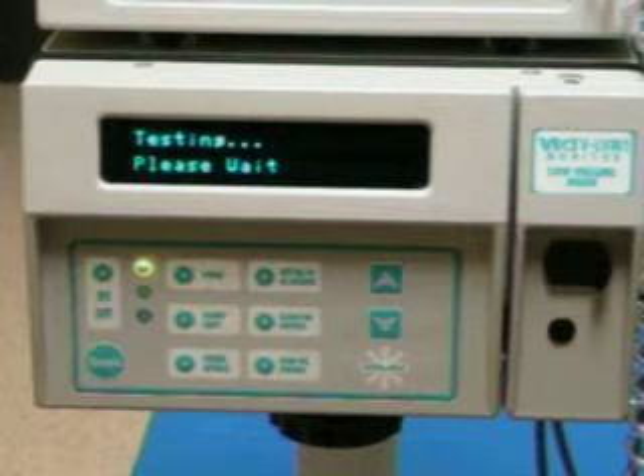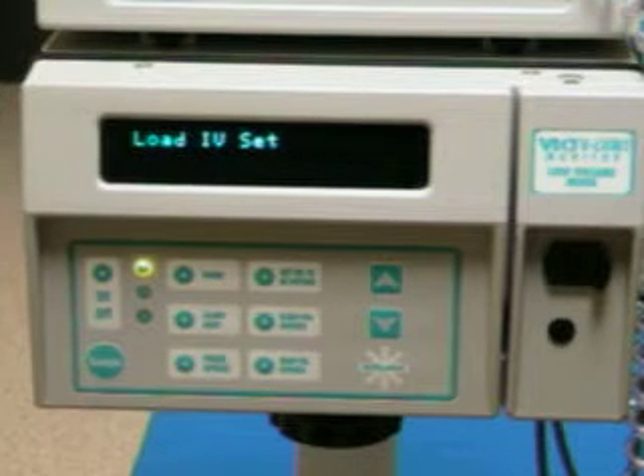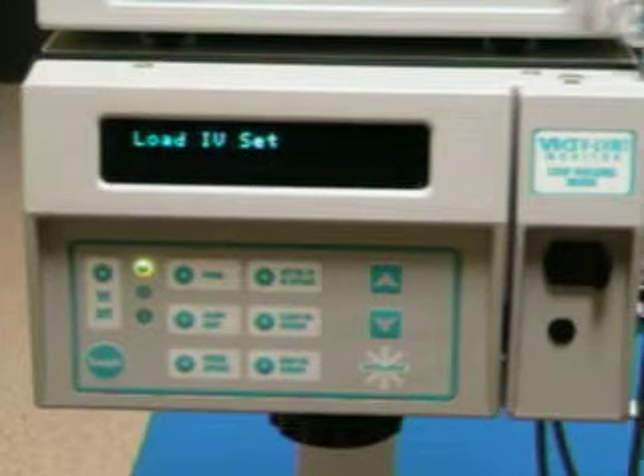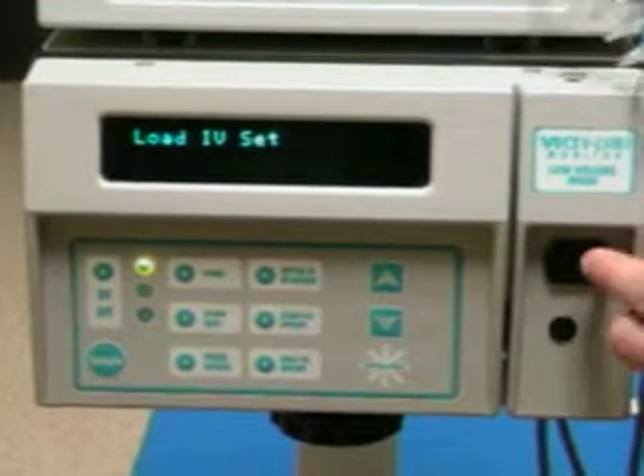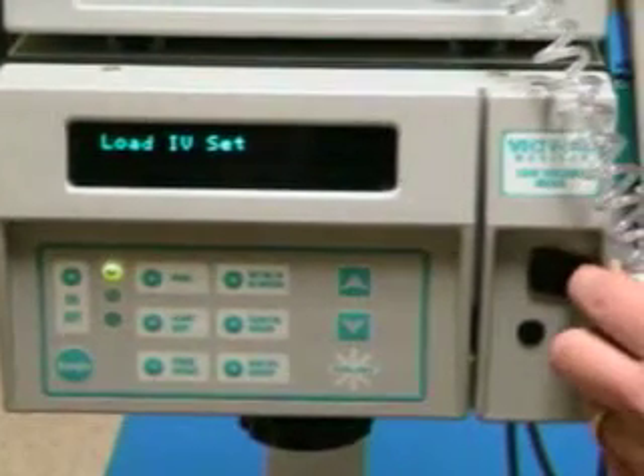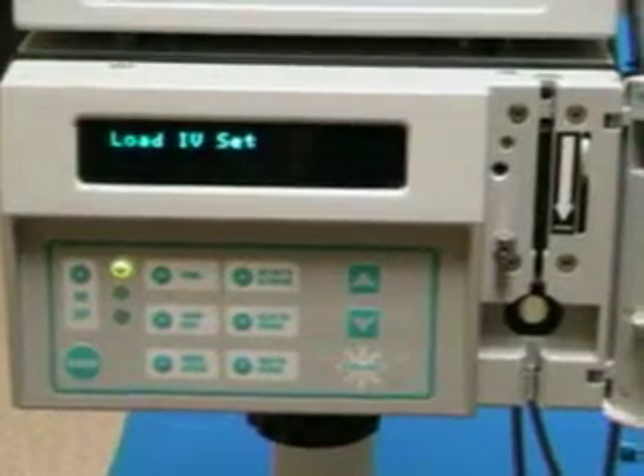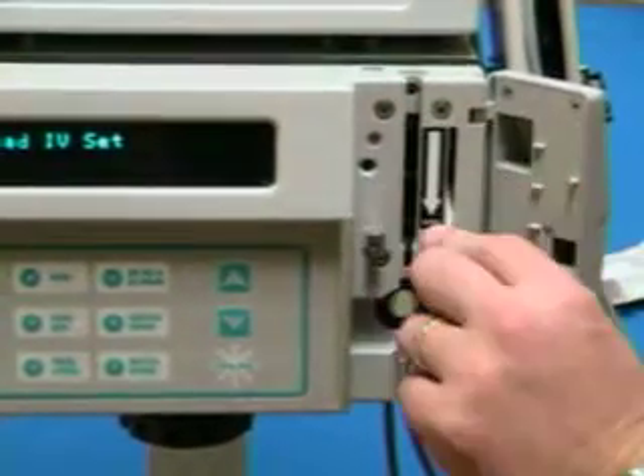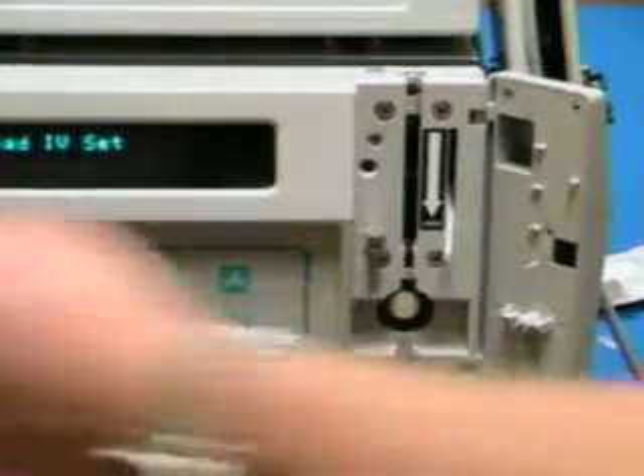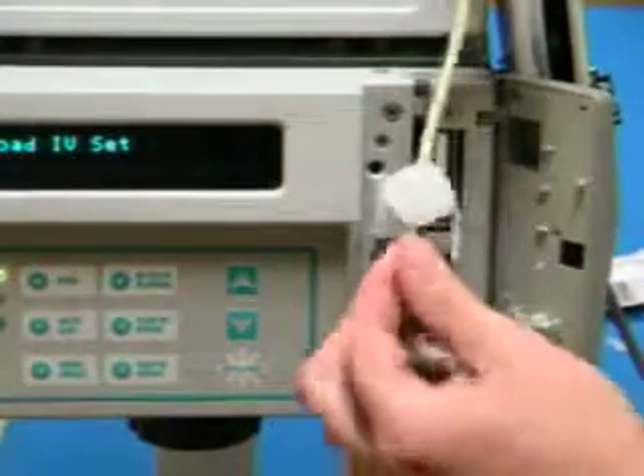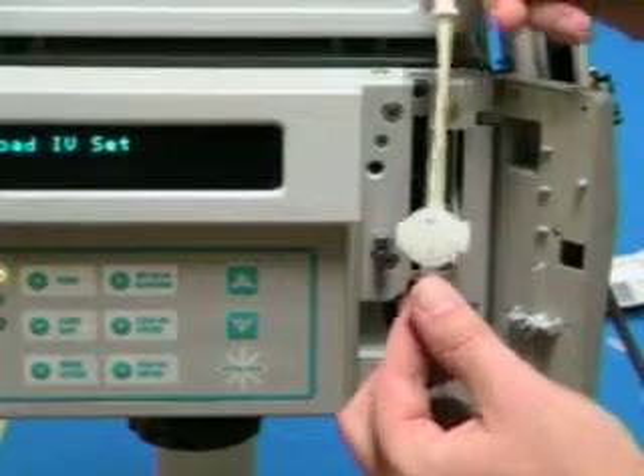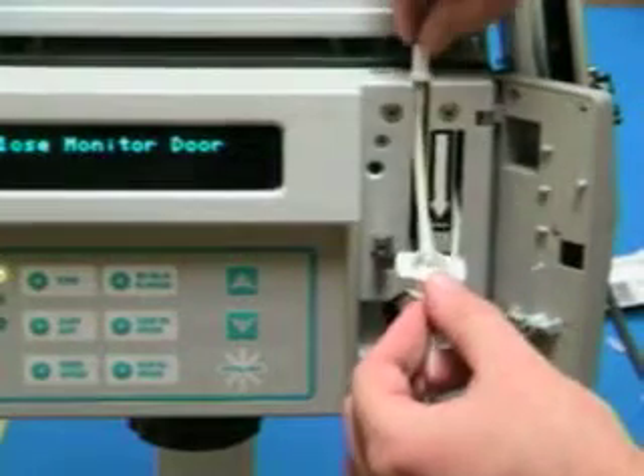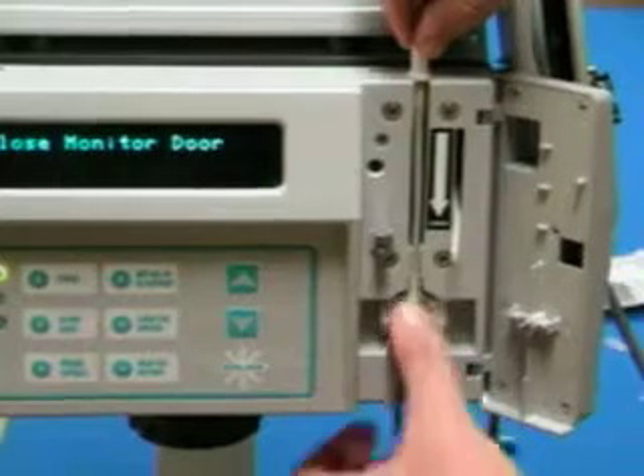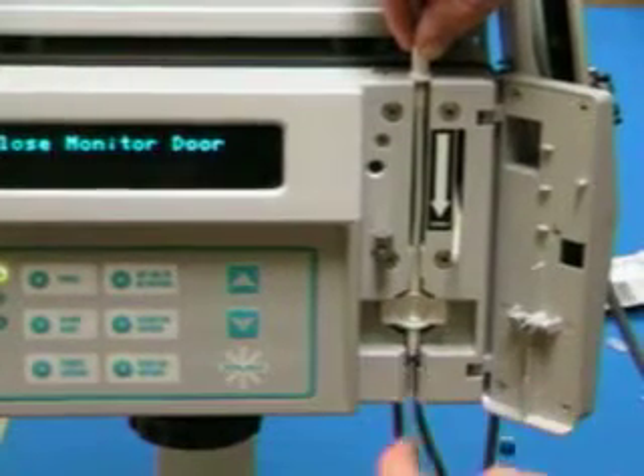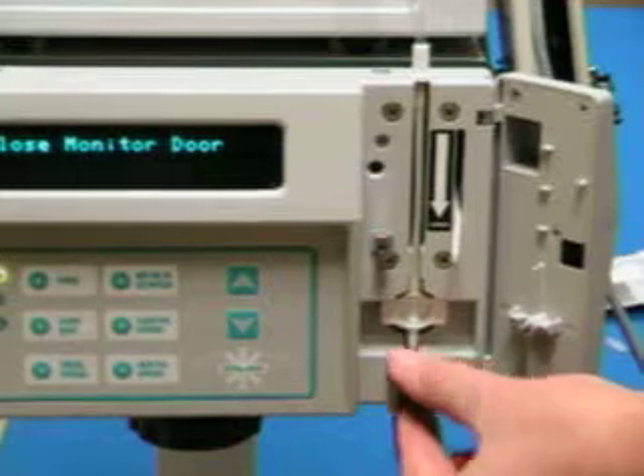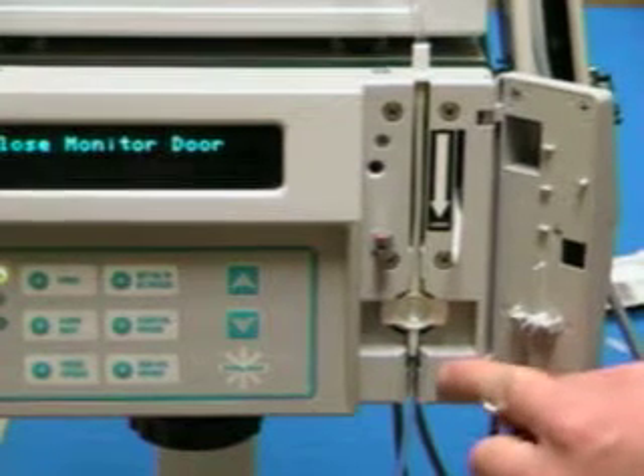It's going to go through a testing mode first, and then the first thing we're going to see is load IV set. So the easiest way to do that is push the black lever to the side. That opens up. We're going to flip the white lever down, and we're going to bring over our IV set. Always put the pressure disc towards the machine. Start off like this. Top end first, stretch it down, and again that pressure disc towards the machine, and the clear tubing fits in between. There's two black sensors down here. We want to keep these clean at all times.